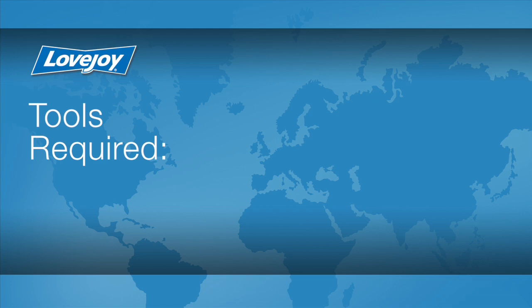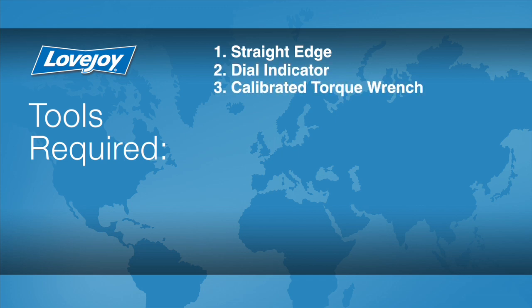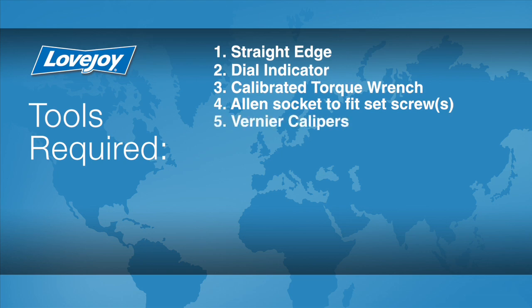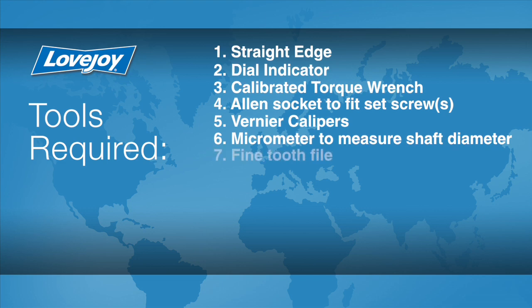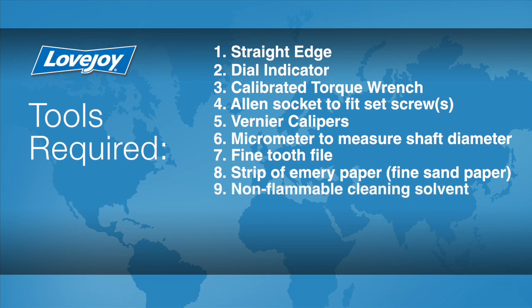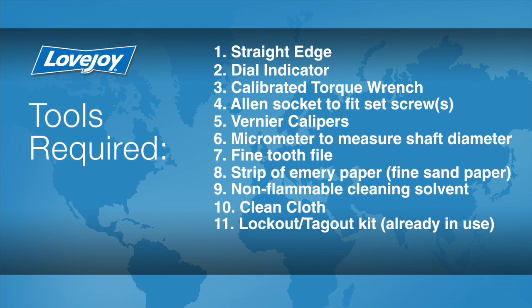Let's look at the necessary tools we will need to perform this installation: a straight edge, a dial indicator, a calibrated torque wrench, Allen socket to fit the set screws, Vernier calipers, a micrometer to measure the shaft diameter, a fine tooth file, a strip of emery paper, non-flammable cleaning solvent, a clean cloth, lockout tagout kit, safety glasses, and rubberized gloves.